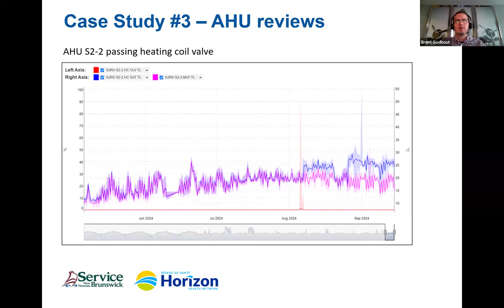Talked about those compounding effects. So one might think, oh, it's just a small thing when you're passing a little bit on your heating coil valve, so it can wait. We'll get to it eventually. But in this case, as you can see here, this red line, I know it's red, it'd be better if it was blue, but it's the heating coil valve. And it's 100% open. So we're trying to meet our set point, and we're not. So it's just remaining wide open the whole time.